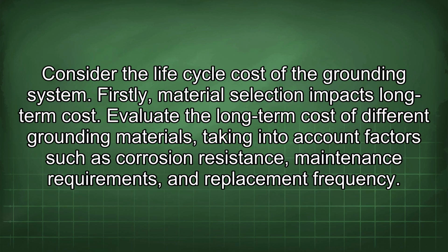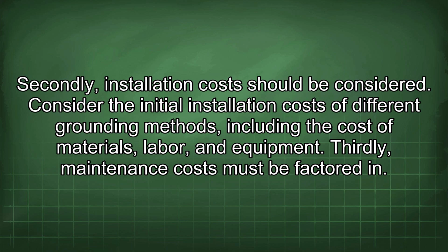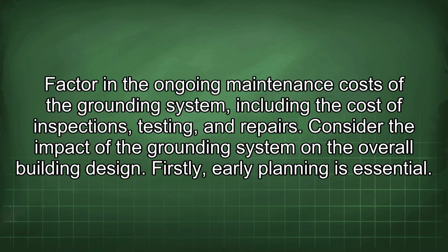Consider the life cycle cost of the grounding system. Firstly, material selection impacts long-term cost. Evaluate the long-term cost of different grounding materials, taking into account factors such as corrosion resistance, maintenance requirements, and replacement frequency. Secondly, installation costs should be considered. Consider the initial installation costs of different grounding methods, including the cost of materials, labor, and equipment. Thirdly, maintenance costs must be factored in. Factor in the ongoing maintenance costs of the grounding system, including the cost of inspections, testing, and repairs.